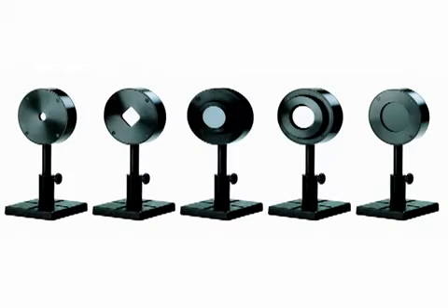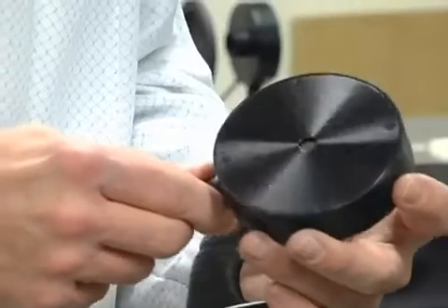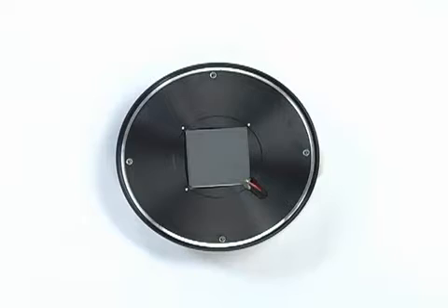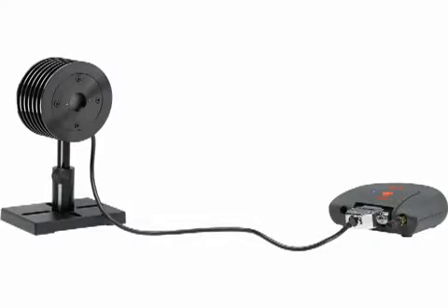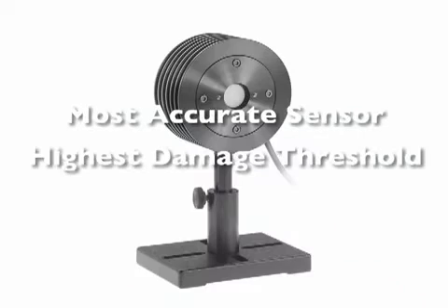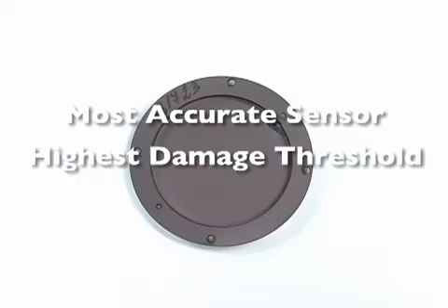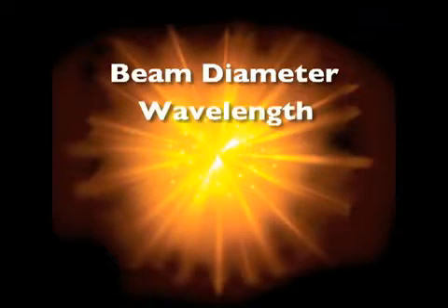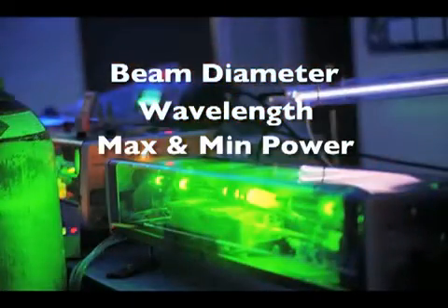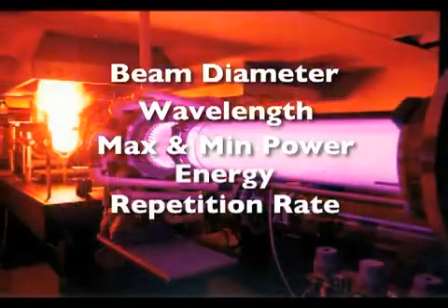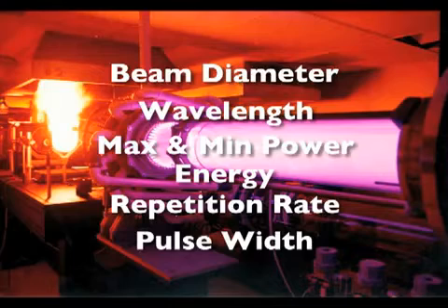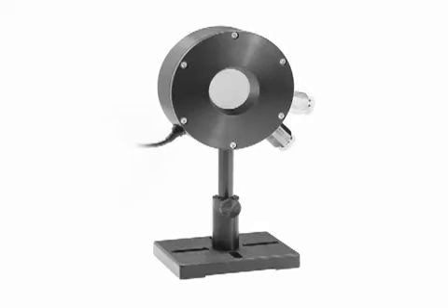Ophir has developed different sensors to measure long pulses, short pulses, and continuous radiation. Ophir's commitment to engineering excellence assures you of having the most accurate sensor with the highest damage threshold on the market today. Laser parameters such as beam diameter, wavelength, maximum and minimum power, energy, repetition rate, and pulse width combine to determine which sensor is the most appropriate for your application.